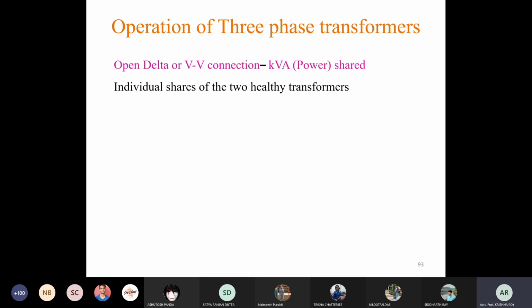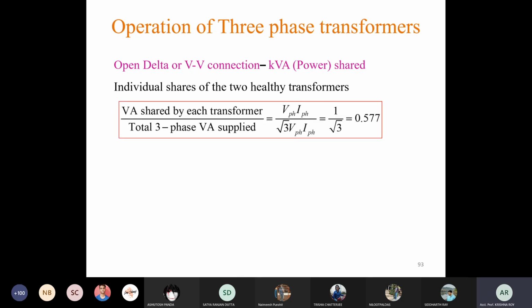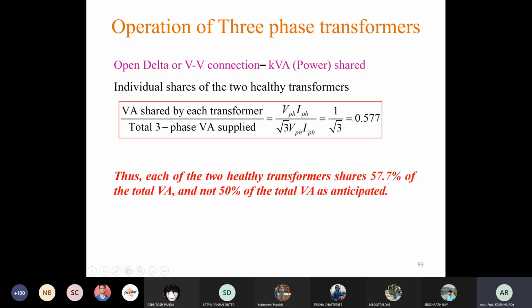Now individual shares of the two healthy transformers. What will be the individual share? Here VA shared by each transformer is V phase I phase, and the total three phase VA supplied is root 3 V phase I phase. So individual share is 1 by √3, which is 0.577. That means each of the two healthy transformers shares 57.7% of the total VA and not 50% of the total VA as anticipated. Here each transformer is sharing 57.7%, not 50%.